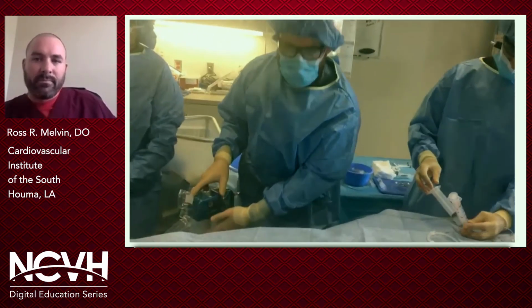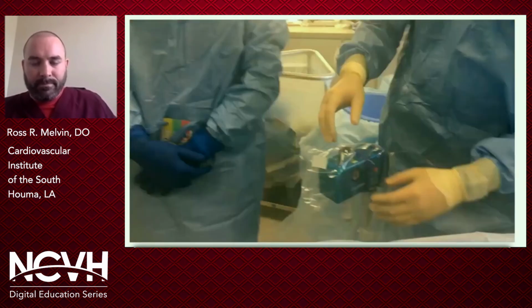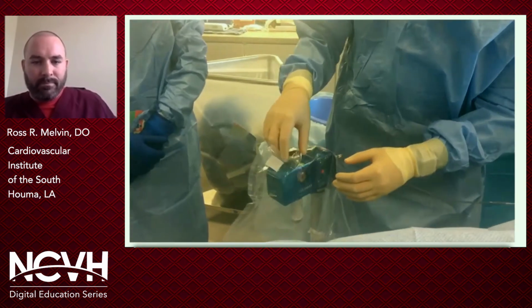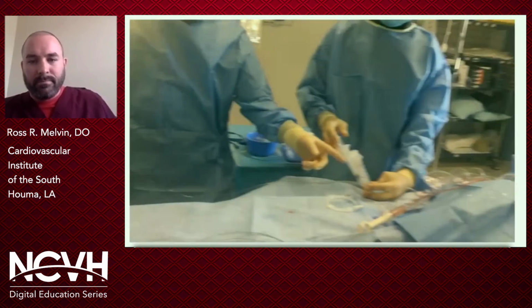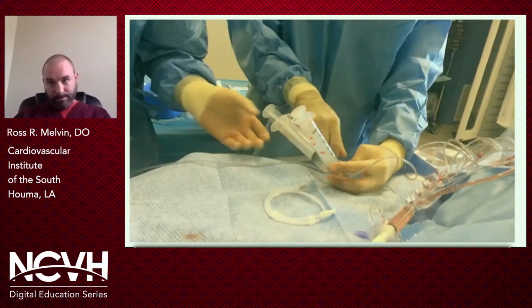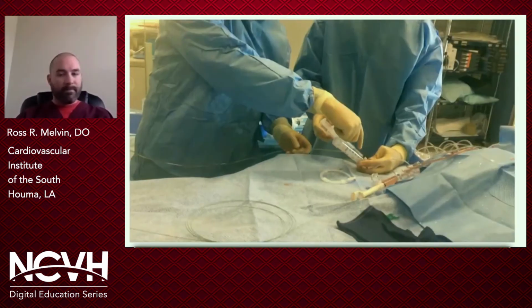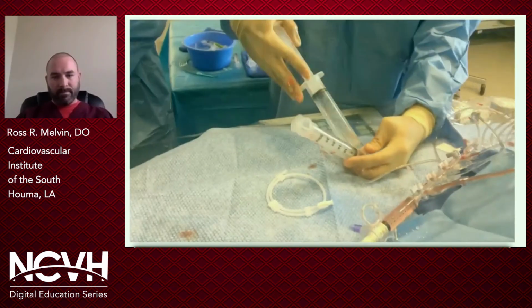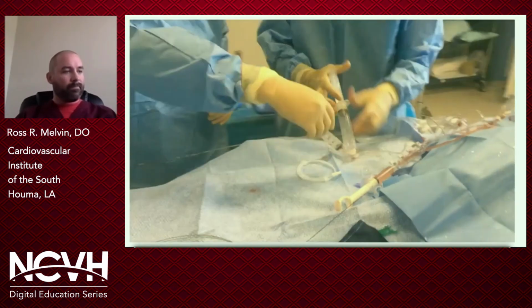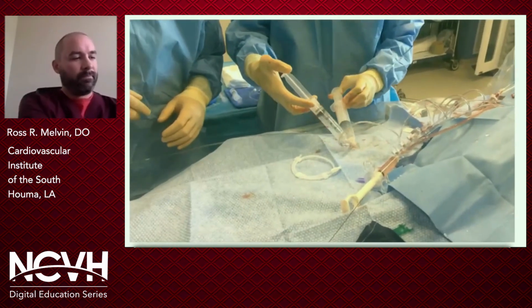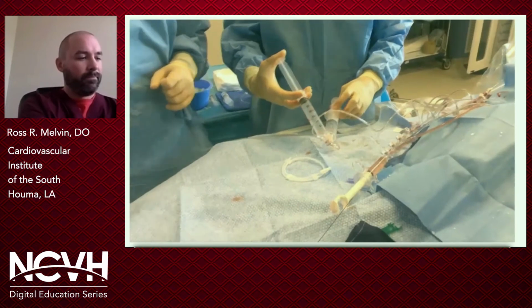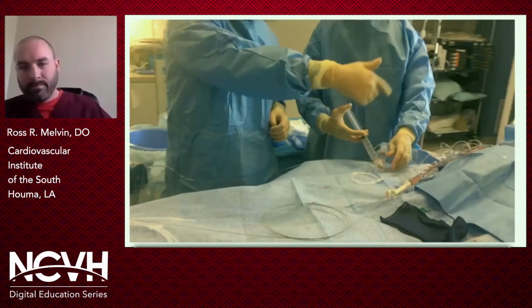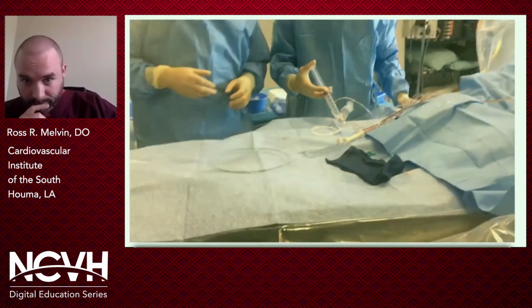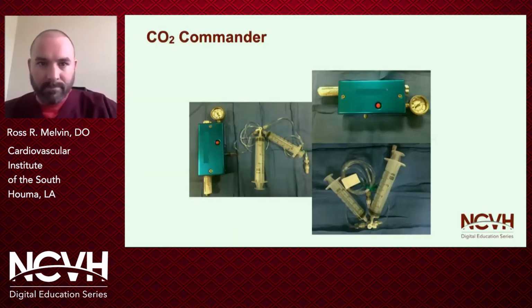Device for the CO2 angiography. Basically, you have a little cartridge here that holds the CO2 so you can get multiple injections. There's a knob here to adjust how much CO2 is being filled into the 60 cc syringe. Then you hit this little red button, and this tube is hooked up to this syringe, and it fills up the syringe. And then you toggle over to fill up the second 20 cc or 30 cc syringe. That's how many cc's you're using for each injection. And then you toggle over to the patient, open, and administer the CO2.